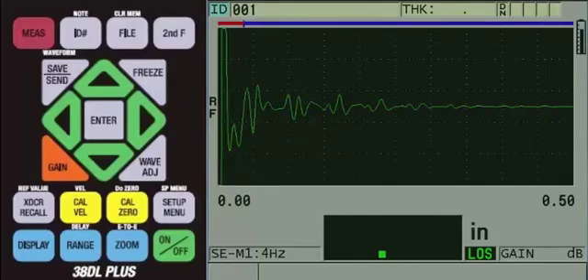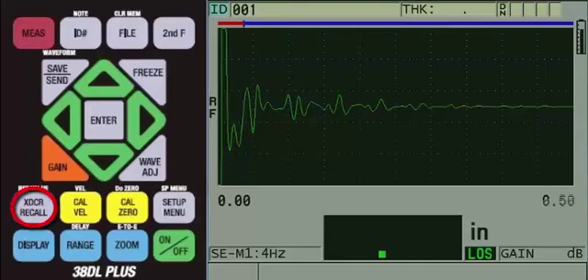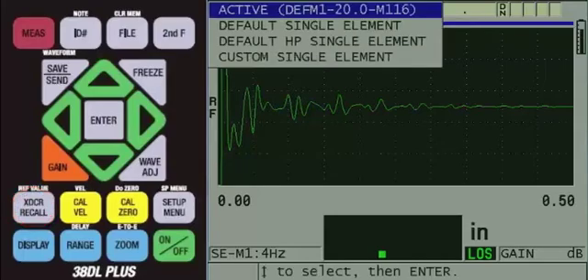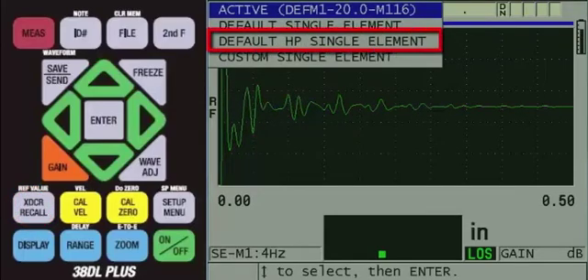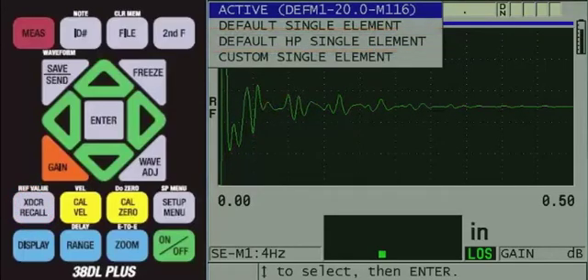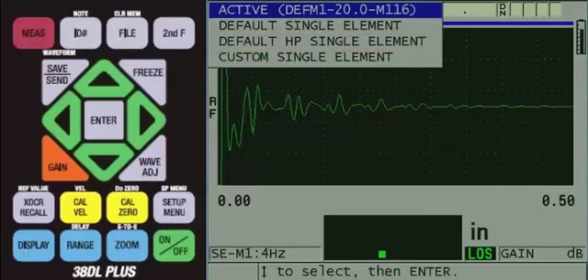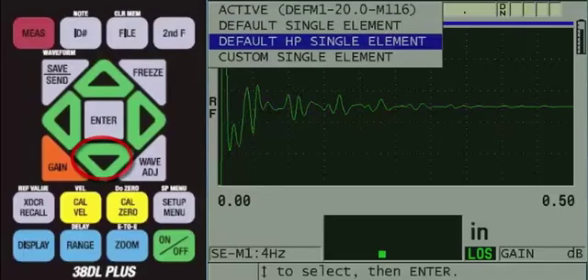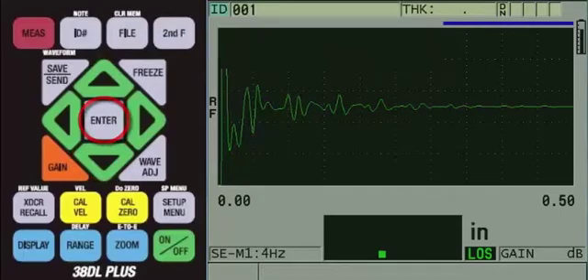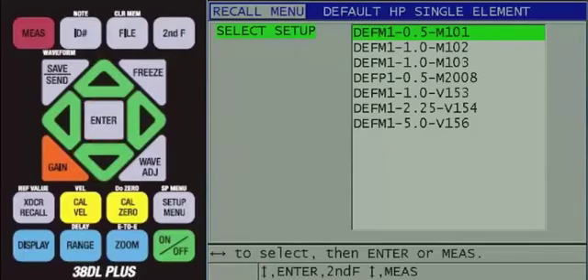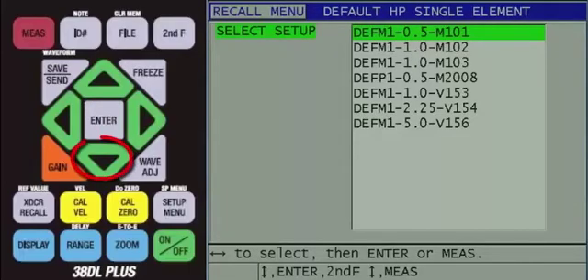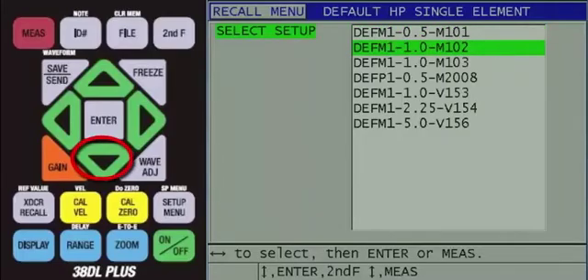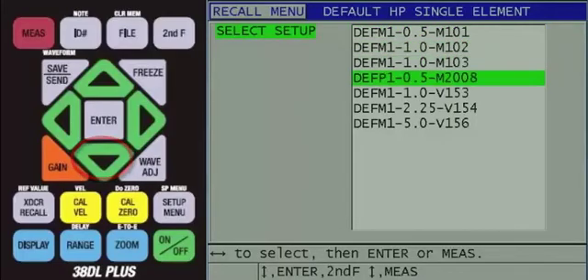Once the instrument is on, press the XDCR recall key. Since the high penetration software option is activated on this unit and we are using a high penetration transducer, we can press the down arrow to highlight default HP single element and then press the enter key. Here, you will see the list of default HP single element transducer setups. Press the down arrow to highlight DEFP1-0.5-M2008.